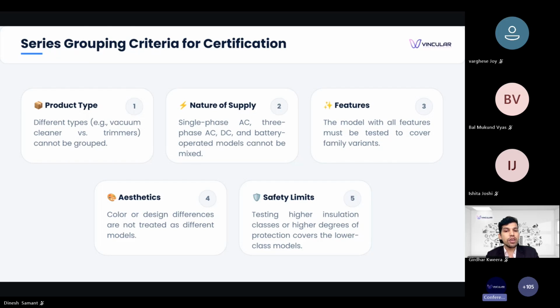Look and color. Changing the color or appearance does not count as a new model, so a color variant doesn't need to be tested separately. Insulation class. If a higher insulation class has been tested, other models in the group with a lower class are automatically covered, so no separate test is needed. Degree of protection. If a higher protection level has been tested, then the models with a lower protection level in the group are covered too. So to sum up, series grouping cuts down on repeat testing, but it is strict about product type and power supply, while being flexible on color, insulation, and protection level.